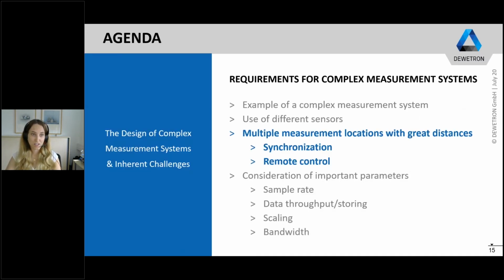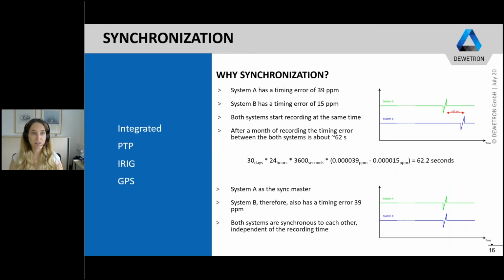So then we come to the next topic, the multiple measurement locations with great distances. Therefore, the synchronization and the remote control are very important to consider. But why do we even need synchronization? I would like to explain it with a small example. If you have system A, which has a timing error of 39 ppm, and system B has a timing error of 15 ppm, and both systems start recording at the same time, you get a timing error between the systems of about 62 seconds, so 1 minute between both systems after a month of recording.